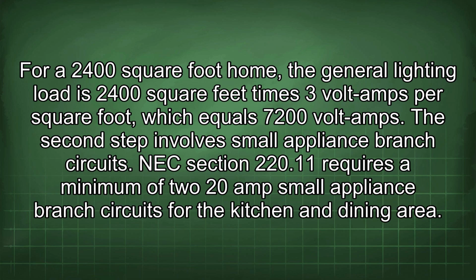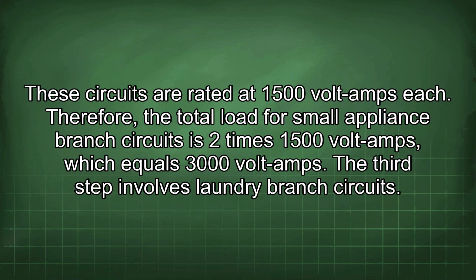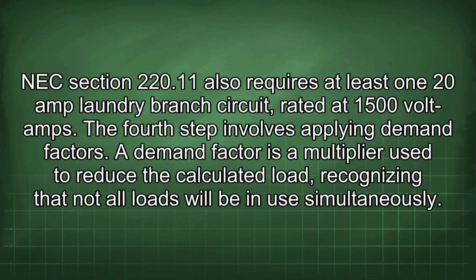The second step involves small appliance branch circuits. NEC Section 220.11 requires a minimum of two 20 amp small appliance branch circuits for the kitchen and dining area. These circuits are rated at 1500 volt amps each. Therefore, the total load for small appliance branch circuits is 2 times 1500 volt amps, which equals 3000 volt amps. The third step involves laundry branch circuits. NEC Section 220.11 also requires at least one 20 amp laundry branch circuit, rated at 1500 volt amps.